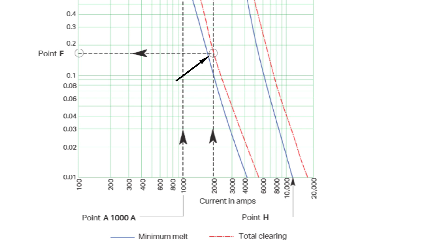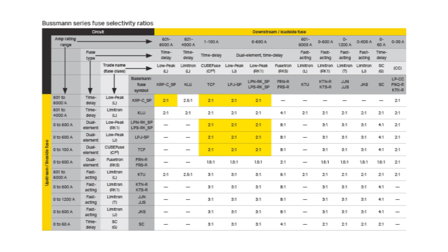For overcurrents up to approximately 11,000 amps, shown at point H on the graph, it can be determined that these two fuses selectively coordinate, since there isn't any overlap on the curves, and the current is less than where the 400 amp upstream fuse crosses 0.01 seconds. When overcurrents exceed this value, selective coordination cannot be determined by using time current curves alone. Fuse selectivity ratio tables must be consulted. Using the Bussmann series fuse selectivity ratio table makes it simple to determine whether fuses selectively coordinate and eliminates the need for plotting time current curves.